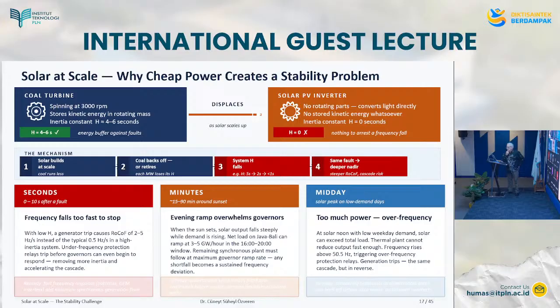After the first 10 seconds after a fault, the frequency falls too fast to stop. With low inertia, a generator trip causes a rate of change of frequency of 2 to 5 hertz per second instead of the typical 0.5 hertz. Under-frequency protection relays trip before governors can even begin to respond, removing more inertia and accelerating the cascade.